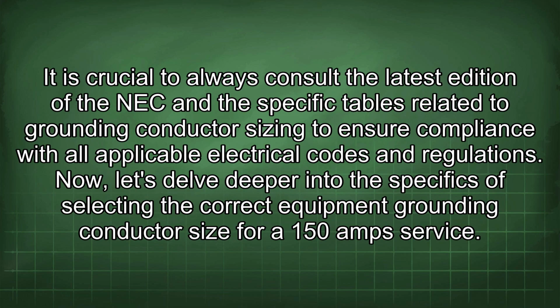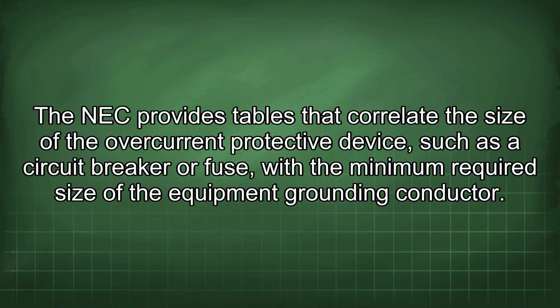It is crucial to always consult the latest edition of the NEC and the specific tables related to grounding conductor sizing, to ensure compliance with all applicable electrical codes and regulations. Now let's delve deeper into the specifics of selecting the correct equipment grounding conductor size for a 150 amp service. The NEC provides tables that correlate the size of the overcurrent protective device, such as a circuit breaker or fuse, with the minimum required size of the equipment grounding conductor.